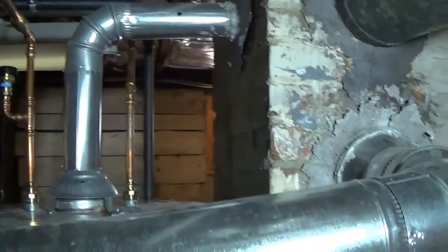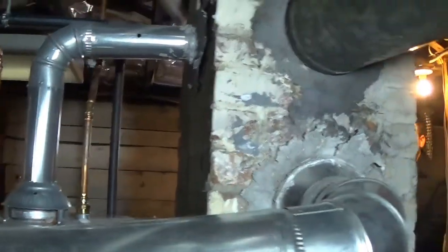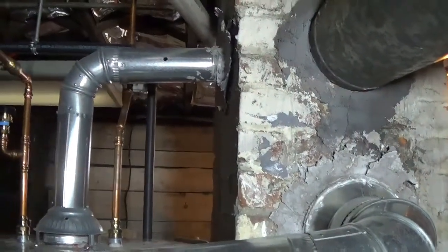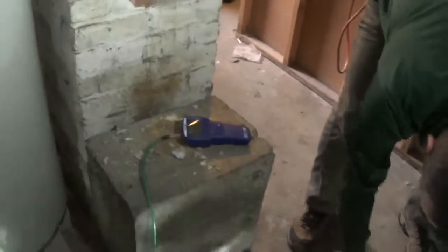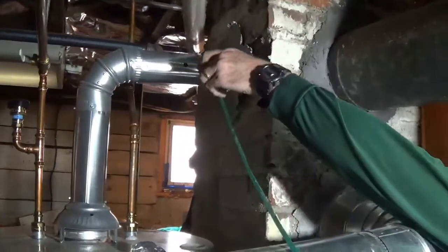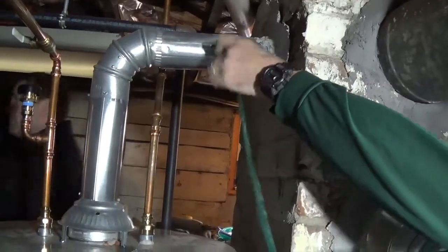So far, actually, you know what? We circle that after we've tested it all different ways to Sunday, right? Not done with that yet. But now we're testing the draft on our domestic hot water tank. I have my manometer still sitting back here, and I run that into the domestic hot water flue. Look at my number. I've got a better negative number now. House isn't fighting as hard. So I got a minus 6.9 or minus 7.1-ish. Minus 7.1. So I write that number down.